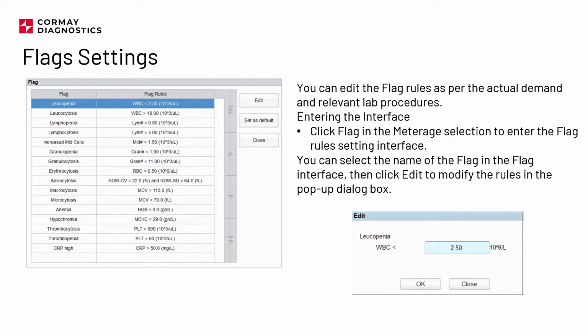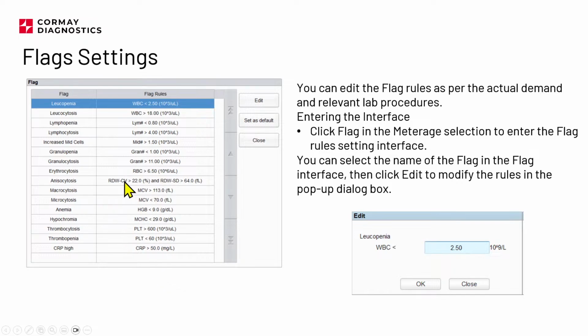Flag settings. This is a window displaying the specific flags, for example when the number of white blood cells is lower than 2.5 thousand per microliter, right? We say leukocytopenia, and leukocytosis when it is higher than 16,000. So a high number of white blood cells, or a low number of white blood cells, sorry. The same goes for lymphocytes, mid-sized cells, granulocytes, and for red blood cells, as I said, macrocytosis, big red blood cells, microcytosis, small red blood cells. This is the standard set of flags set on the analyzer.